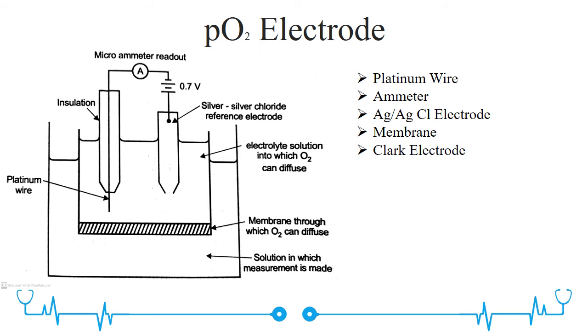A voltage of 0.7 volts is applied between the platinum wire and the reference electrode using a battery. The negative terminal is connected to the platinum wire through an ammeter. Reduction of oxygen takes place at the platinum wire. An oxidation-reduction current is developed which is proportional to the partial pressure of the diffused oxygen.